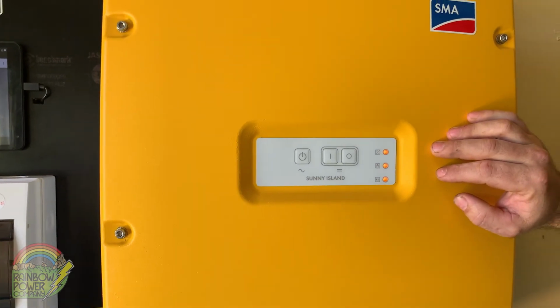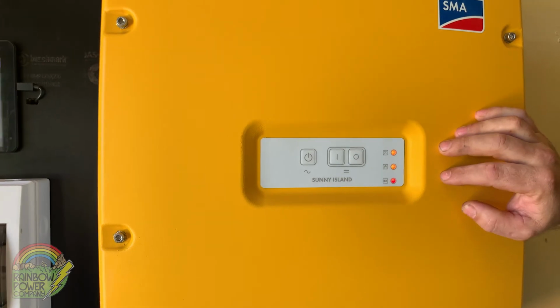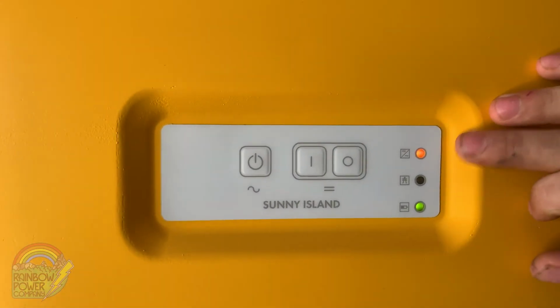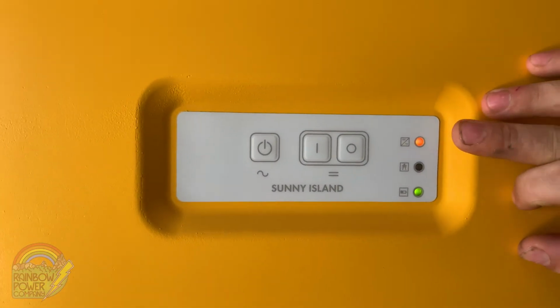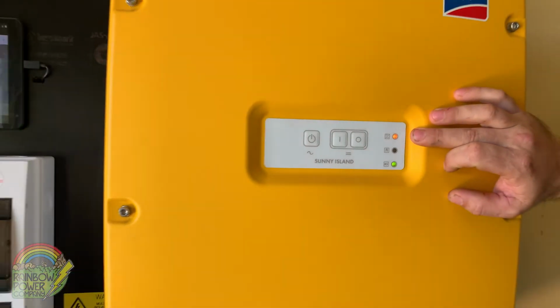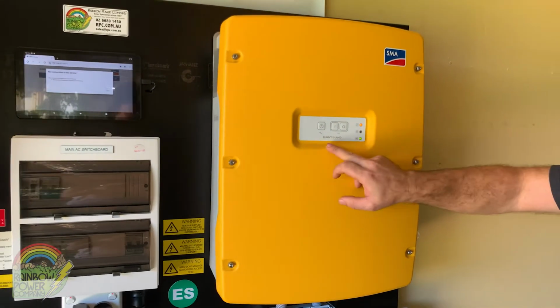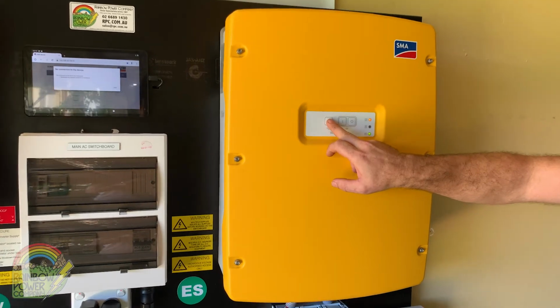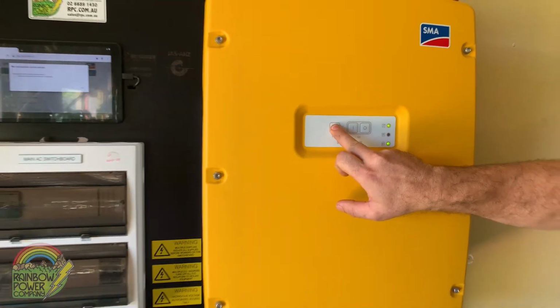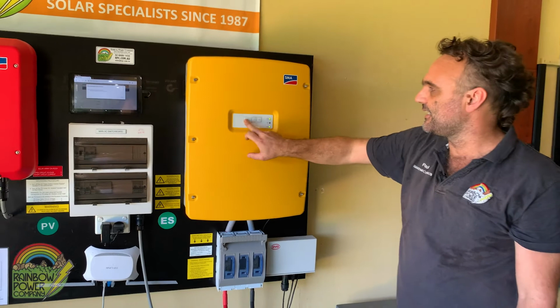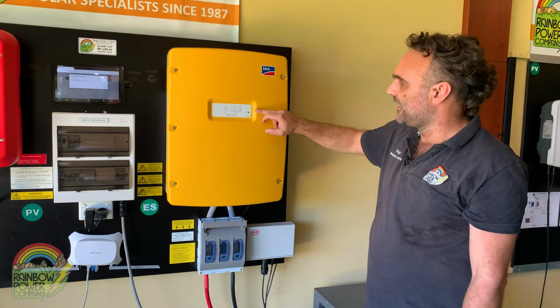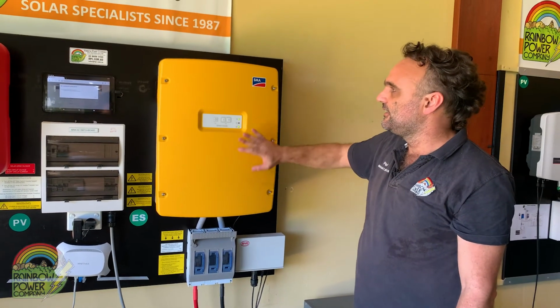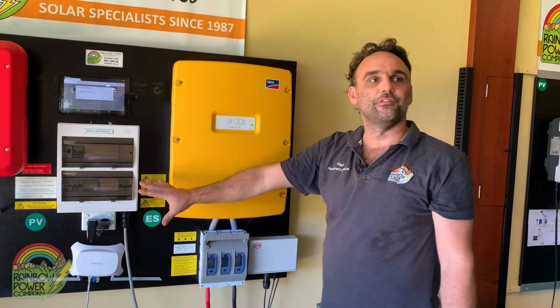We see it blink yellow, the battery light comes on, and our inverter light is yellow at the moment - this means the inverter's in standby. To get the inverter operational, we need to hold the on-off button, or run button, for a few seconds until the Sunny Island beeps and the light turns green. That means the Sunny Island's producing 240 volt power.